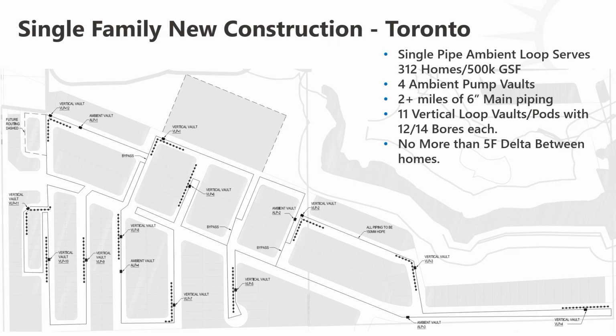The key to a single pipe is having those distributed resources and injecting in multiple places. Otherwise you don't save pump energy, you don't save your flow rate and pipe size, and costs go up because you're putting all the energy in one location. I've seen other designs with just one spot to put energy in, and then a single pipe probably doesn't make sense, because you have to over-pump compared to a two-pipe. The idea of the single pipe is distributed energy to distributed buildings.